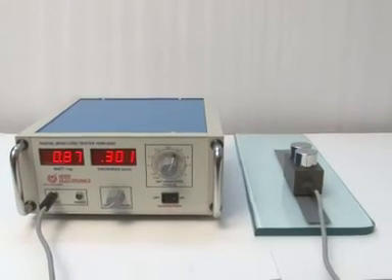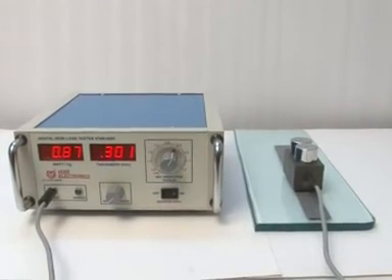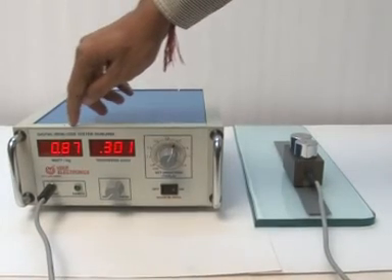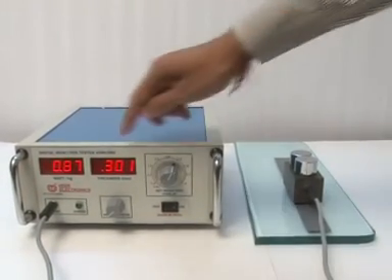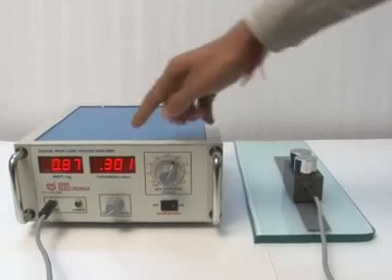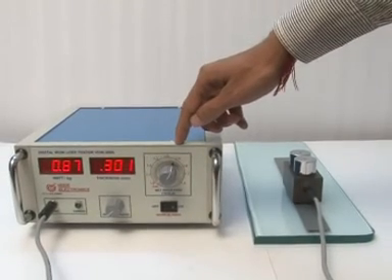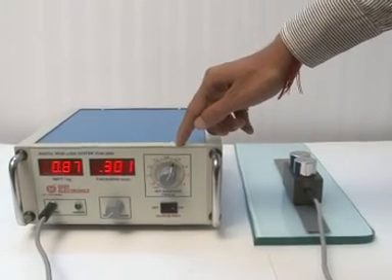Now note down your reading. This is the watt per kg of your material. This is the thickness of your material. This is the induction which you have set.